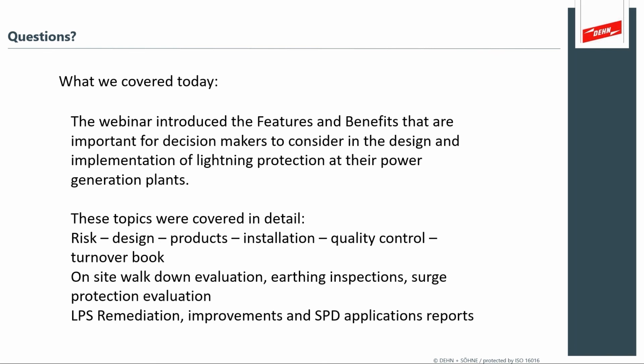The only requirements we have there are that the air termination system is steel, installed and bonded properly to the natural steelwork of the structure, and that the natural steelwork complies with the requirements in the standard. In other words, the electrical continuity of the steelwork from the air termination system to the earth termination system, as well as the minimum thickness requirements, so that we don't get excessive heating of the structure, and there won't be any melting or heating of the natural steelwork. Mark, anything you'd like to add? No, I think that definitely addresses the point: as long as it's thick enough, it won't cause undue heating and rupture.